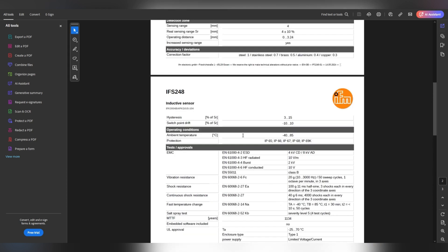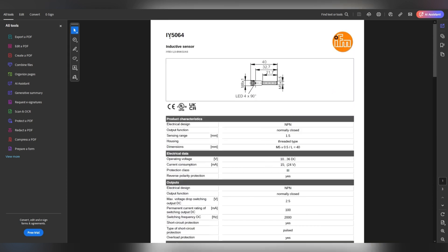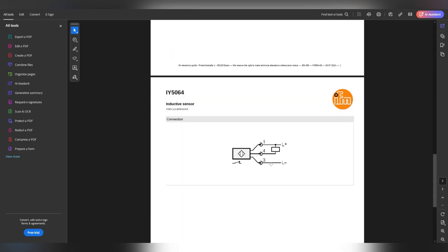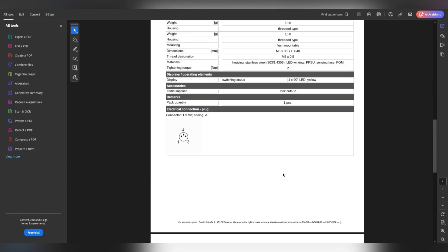And then this one right here is the IY5064 — the NPN sensor, normally closed. When it switches on, as you can see here, it will give zero volts to the load. So basically it always has 24 volts, and when it switches on, it switches on the zero volt and gives that zero volt to the load. That's what's happening with this NPN sensor.